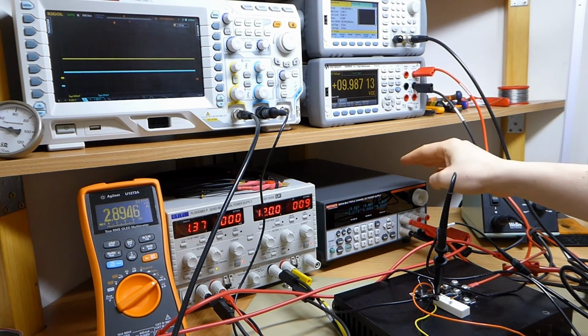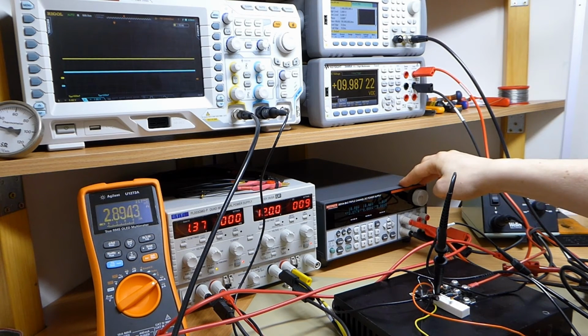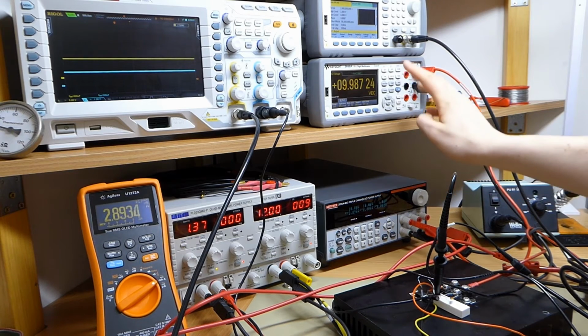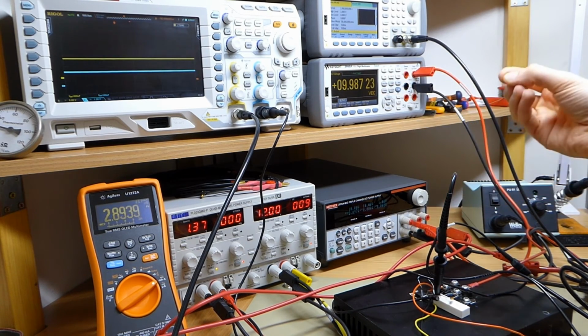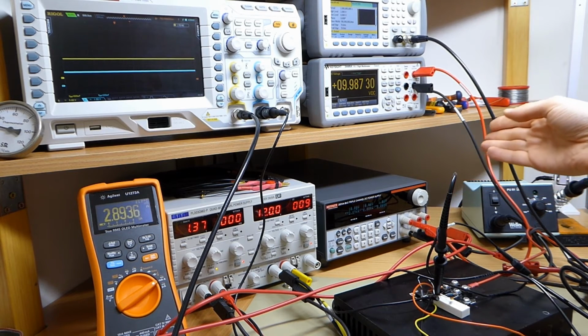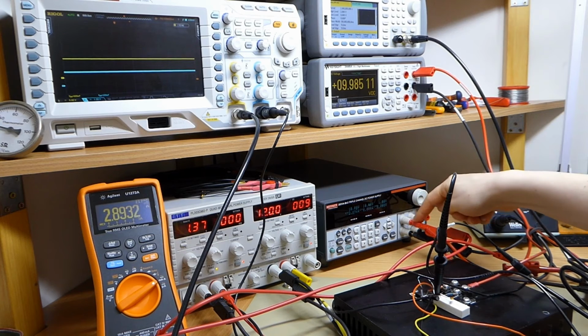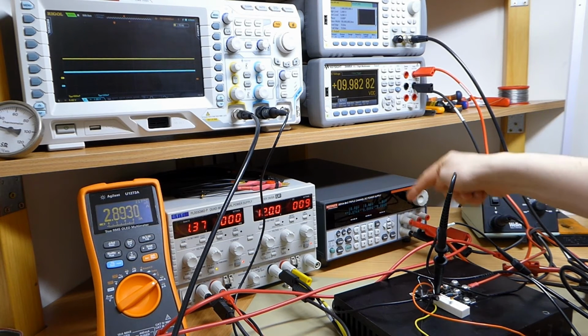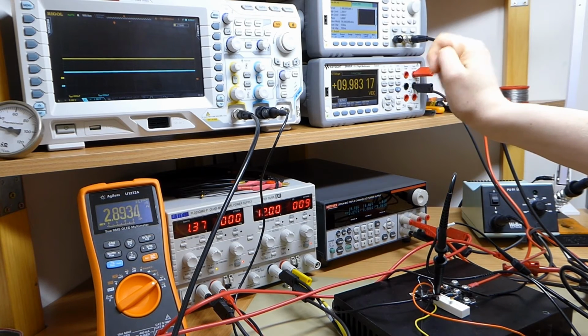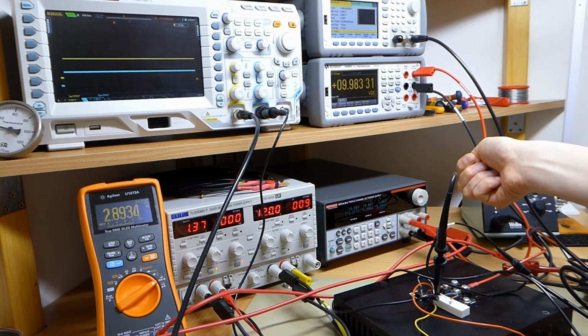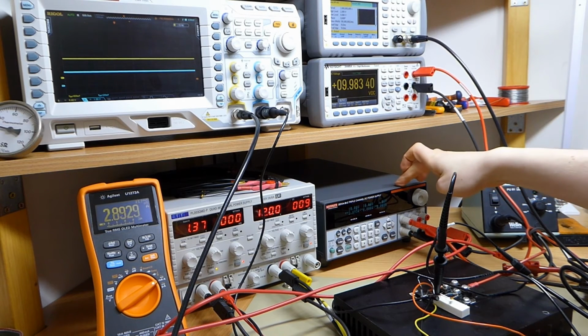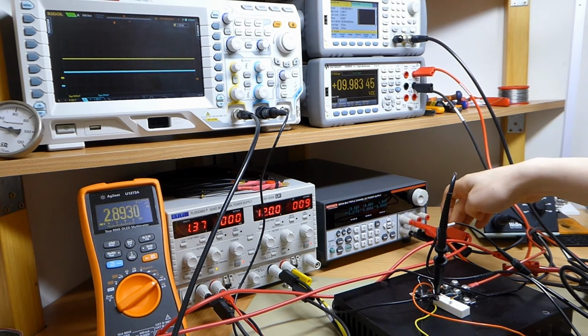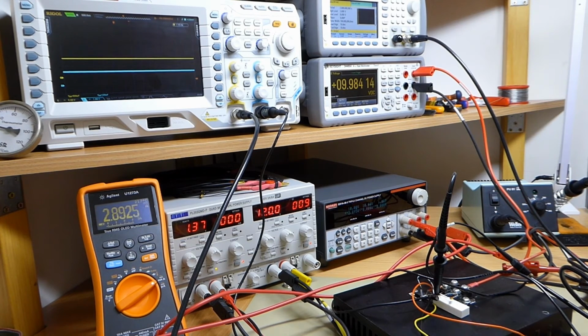According to the specs of the power supply, the load regulation should be around 2 millivolts plus another 4 millivolts at 10 volts output, so about 6 millivolts maximum, but we're seeing a 20 millivolt drop here. This is actually due to the measurement setup in a way, because we're measuring the output voltage at the binding posts, whereas the internal feedback comes from before the binding posts. So this extra drop in voltage is most likely due to the ohmic resistance between where the feedback is done inside the power supply and where we're actually measuring it. Unfortunately there isn't much we can do about that because the power supply doesn't have inputs for external feedback lines, so that's just something we have to live with, I suppose.